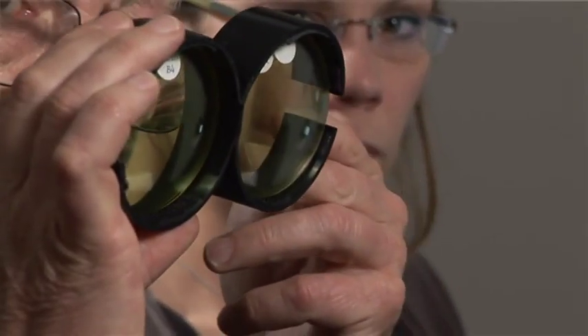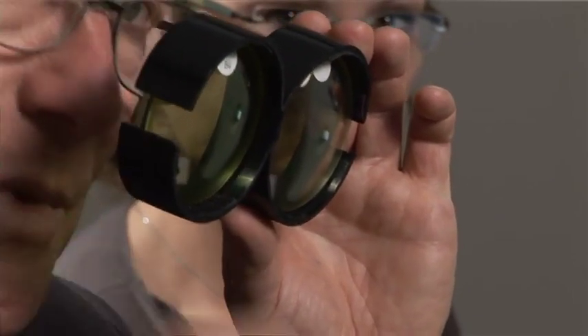and the way I would suggest you do that is to offer up the lenses and then increase the saturation in one eye, decrease it in that eye, and then do the same thing in the other eye. In other words, altering the tint from the binocular standard that you've achieved using the colorimeter. You can use the trial lens program to help you select the lens combinations that you need in order to do this.